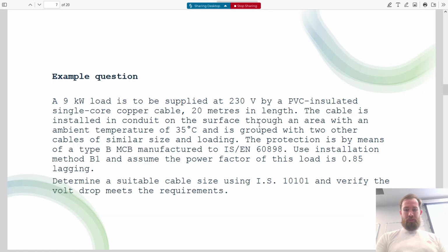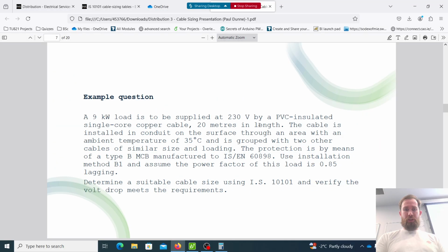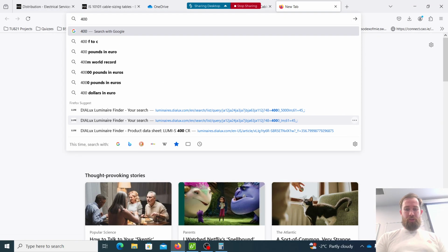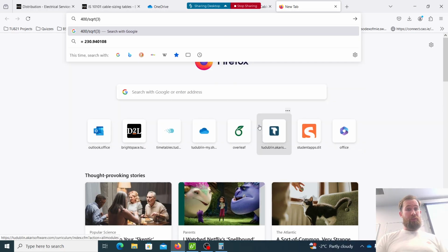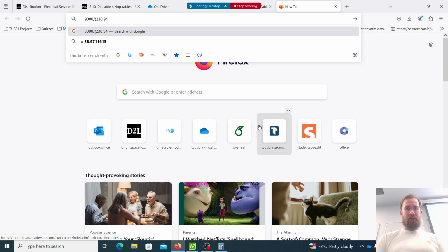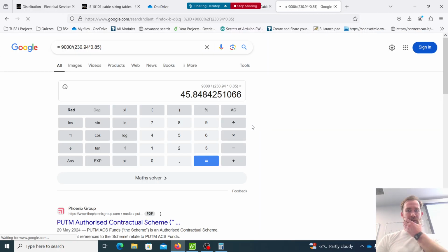Did you go reading about that? No, I haven't looked at it. So you're saying 400 by the square root. Yeah, let's have a look. So function of 11. 400 divided by the square root of 3. Okay. So you're saying 230.94. 9,000 divided by that times 0.85. Oh yeah, good. Well spotted.